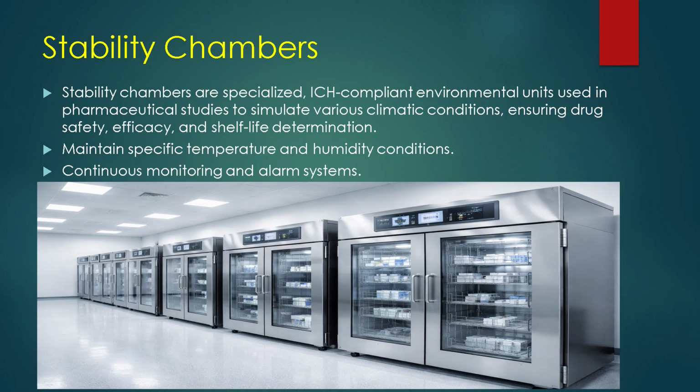Stability chambers are specialized ICH compliant environmental units used in pharmaceutical studies to simulate various climatic conditions, ensuring drug safety, efficacy, and shelf life determination. They maintain specific temperature and humidity conditions. They are equipped with continuous monitoring and alarm systems to ensure that any deviation is immediately detected and controlled.